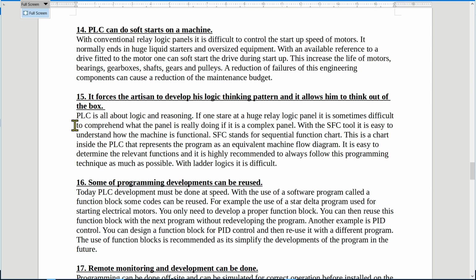Now, for example, today we use an SFC tool. It's easy to understand how the machine is functional and is actually functioning by just looking at the SFC program, because SFC stands for Sequential Function Chart. Now, this chart inside the PLC actually represents the program, the equivalent of the machine flow diagram. And this is highly, highly helpful.